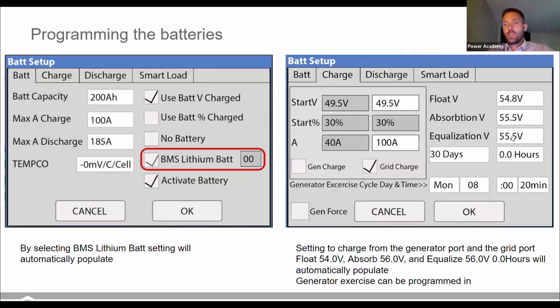Equalization is there for lead acid batteries. It was to provide a high voltage for a short amount of time, about once a month. What that would do is burn off some of the sulfur on the lead acid plates. We don't use that with lithium batteries. You always want to have this set to 0 hours, and that'll just prevent equalization. High voltage on lithium batteries can damage the cells, so it's important not to use that.